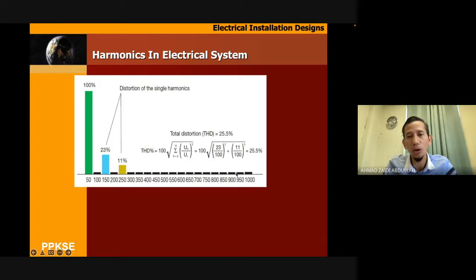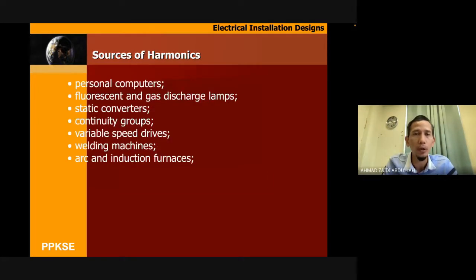Let's say we include all of this odd harmonic, so confirm our total harmonic will become more. So that's the issue related to this topic. We know that another source of harmonic comes from personal computers, your laptop, your desktop, because most of that is electronic devices. So electronic devices will confirm produce very high harmonic. And then fluorescent lamp and gas discharge lamp.